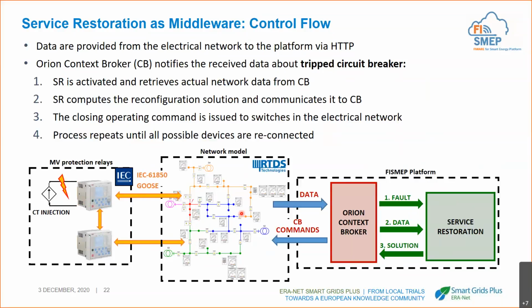On the other side, the data are continuously sent as data streams to the Orion context broker. This component in the platform receives continuously the data from the simulated networks. When it detects that a fault occurred, it informs and initiates the service restoration middlewares, which retrieves the most actual data set. It computes the solution and sends it back for the actuation of closing commands to the simulator to close the switches according to the candidate that has been computed here. And this process repeats until all the loads have been restored.